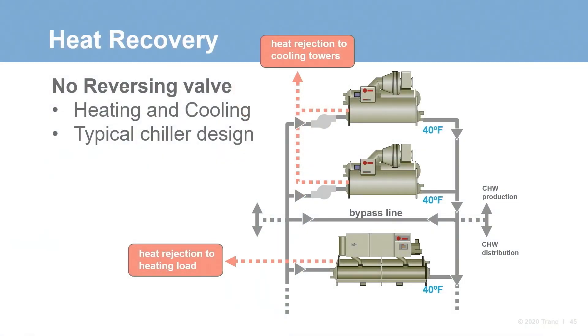The piping layout shown here will be considered preferentially loaded. This means that the heat recovery chiller needs to make the system chilled water temperature because it is sending it directly to the load. In this case, we get what we can get out of the condenser side for heat. Heat recovery chillers can come in numerous sizes, configurations, and compressor technologies. In these examples, we are focusing on water-cooled heat recovery chillers.